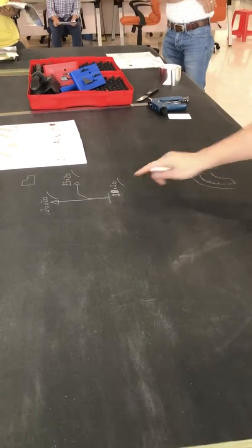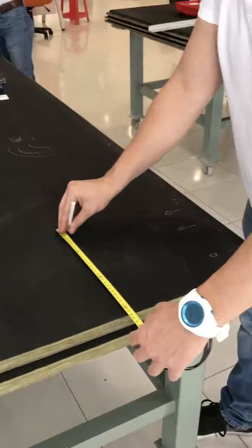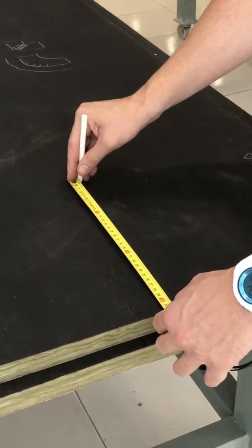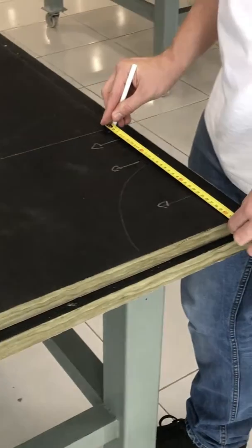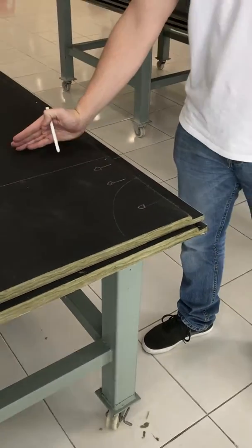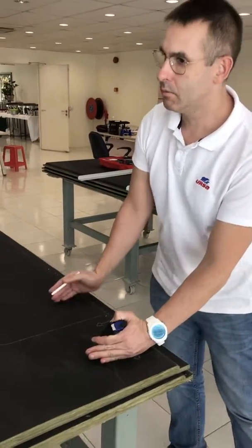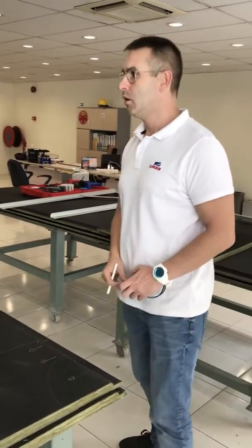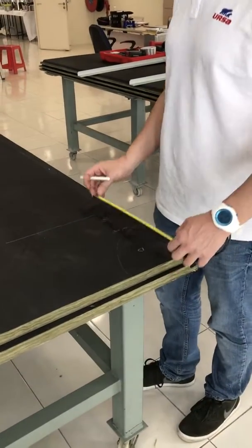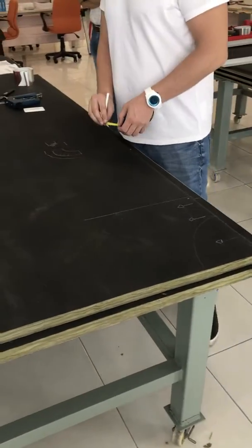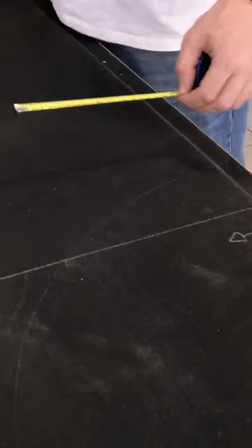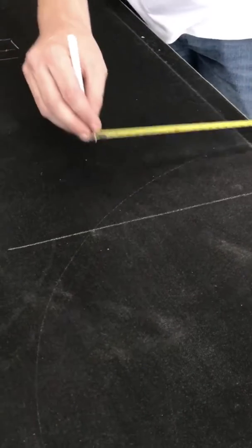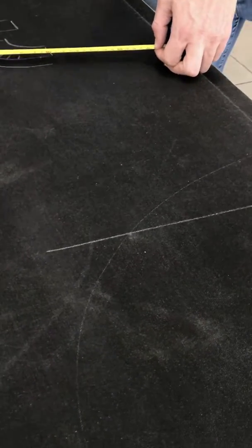Then 30 centimeters width means that I have to make the line at 30 plus 2. You remember, width of the coverings is always 2 centimeters more. Why? Because we have a wall on this side and a wall on this side, 1 centimeter, 1 centimeter, then 32. It's gonna finish at 30. Okay? Radius minimum 20. The radius is the distance from here to here.